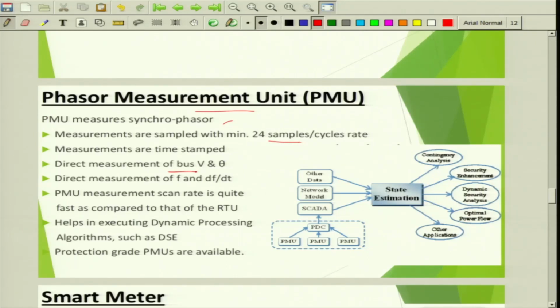PMUs allow direct measurement of bus voltage and angle — this is one such device where you get direct information about phase angle. They also allow direct measurement of frequency and rate of change of frequency, which is important because as more converters are introduced in the future, this rate of change of frequency will play a crucial role, since the inertia of the system is going to decrease.